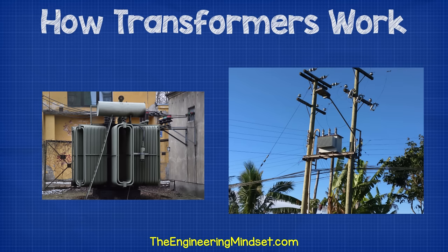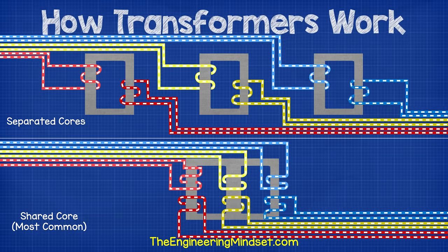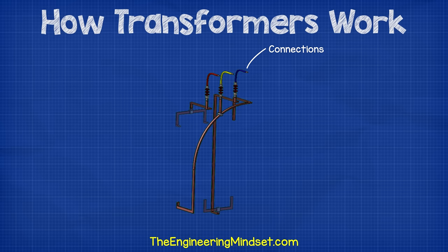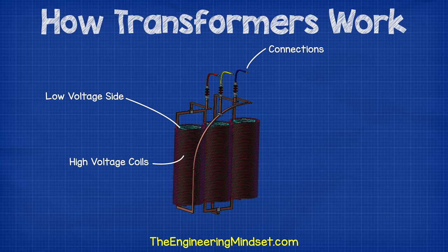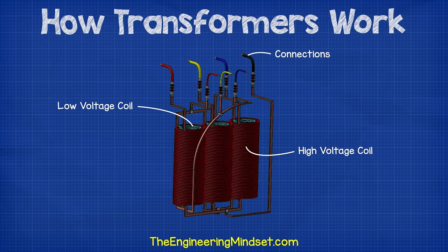The transformers for commercial buildings and power stations are usually in a three-phase configuration. You'll see these placed around your cities and towns. These three-phase transformers can be made from either three separate transformers that are wired together, or they can be built into one large unit with a shared iron core. In this setup, the coils will typically sit concentrically within one another with the higher voltage coil on the outside and the lower voltage coil sitting on the inside. These coils are insulated from one another, so that only the magnetic field will pass between the two coils.